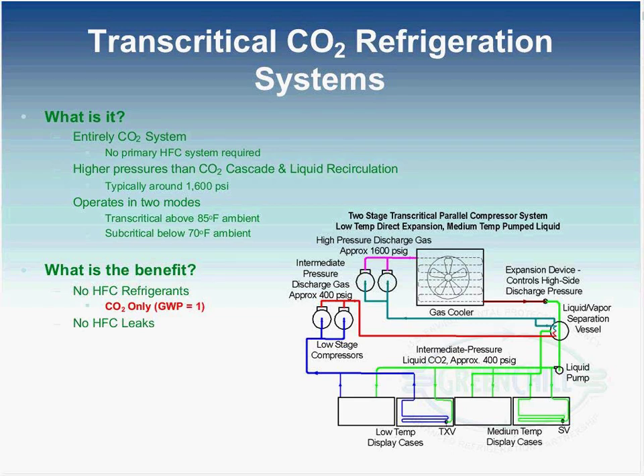I'll explain a little bit about the efficiency of a transcritical system as compared to other systems in just a minute. But the reason why I'm showing you this type of system is in a way to make a transcritical system more energy efficient, by using a two-stage system where we have low-temp compressors for the low-temp side and high-side compressors for the medium-temp side. And you're all using CO2 here, and there's no other refrigerant being circulated.